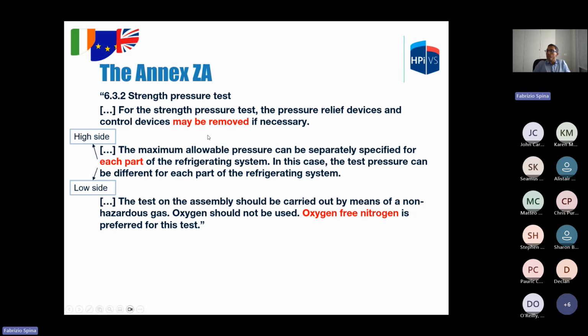As a general note, for the strength pressure test, the safety device may be removed if necessary. The pressure test for each side can be made separately, so one test for the high side and one test for the low side. The preferred fluid is oxygen-free nitrogen.